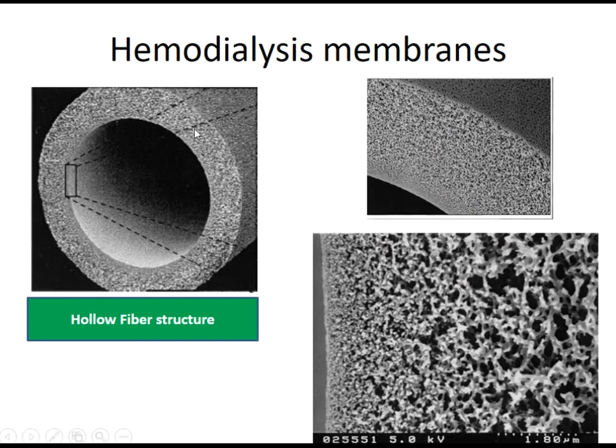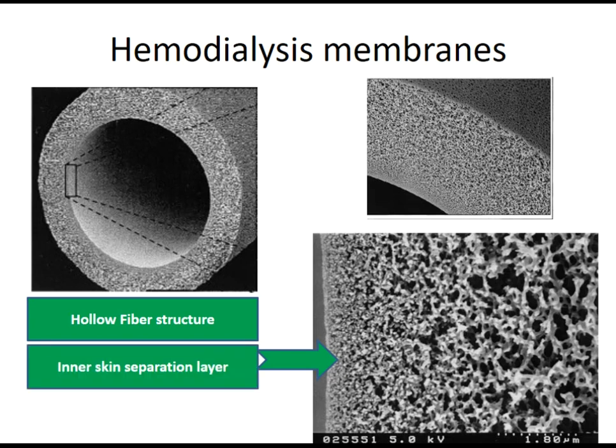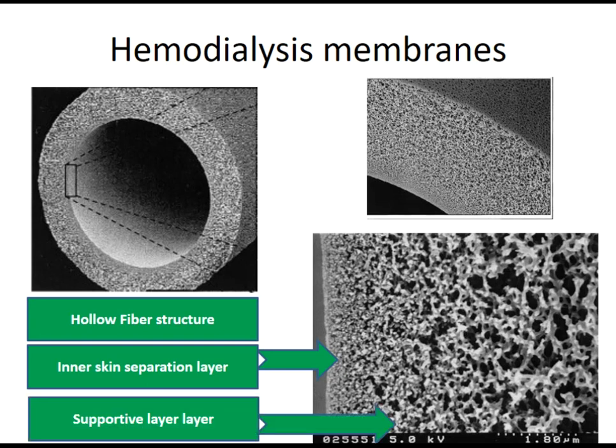Each fiber has a hollow structure forming the blood pathway and a wall. The internal diameter and wall thickness define the fiber structure. Within the wall, there is a separation layer — specifically an inner skin separation layer — which is the most important layer in sieving, determining which solutes or molecules can pass. There is also a supportive layer within the wall.